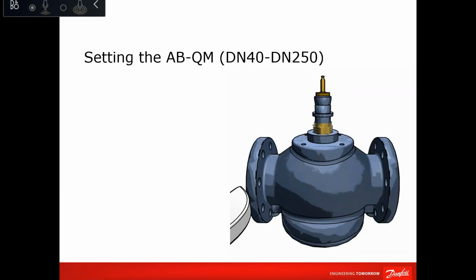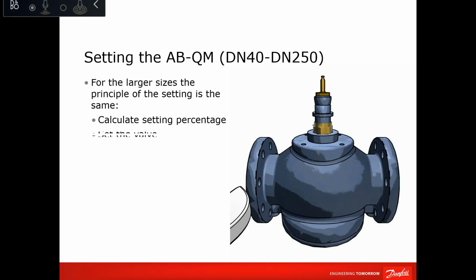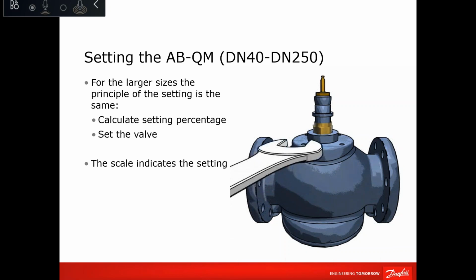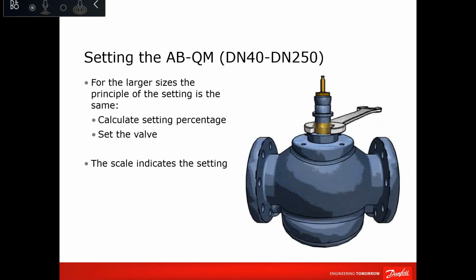Setting of the bigger sizes, DN40 up to DN100, we calculate the same way: design flow divided by the valve nominal flow. The setting percentage is given by us, so there is nothing to worry about. Then use an adjustable spanner: clockwise to increase and anti-clockwise to reduce. It's the reverse of the small size.